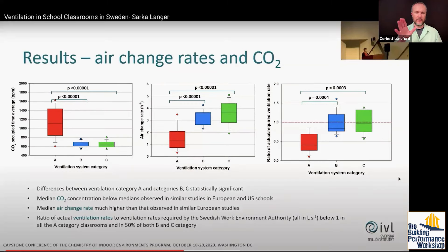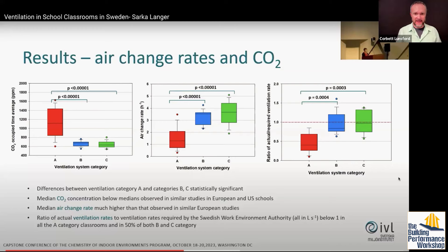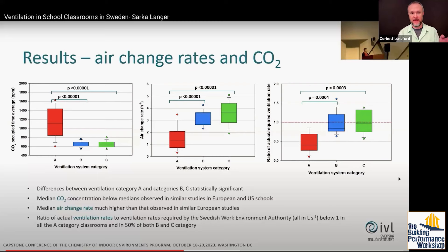On the left graph, the big wide red bar represents the variability in CO2 during occupied classroom time. That's the story of why we don't just open windows. There are many reasons you can't open windows and depend on that — here you see variability ranging from 600 ppm all the way up to 1,600 ppm across classrooms. Of the eight classrooms in category A, three had the Window Master automated system and five relied on manual opening by the teacher.